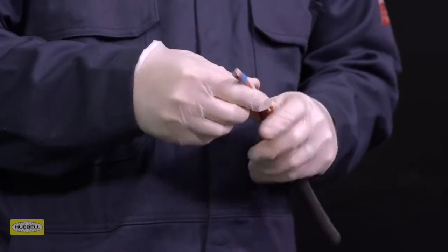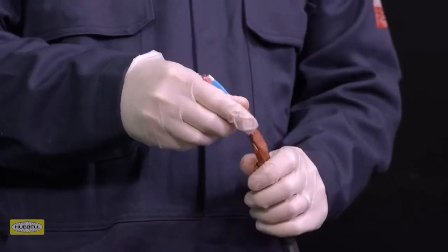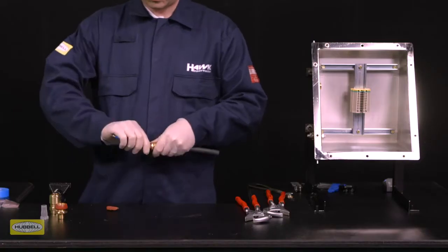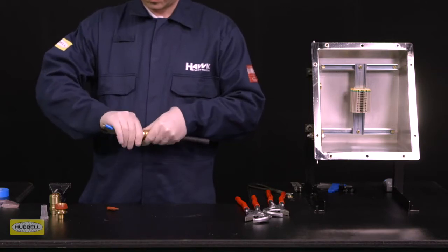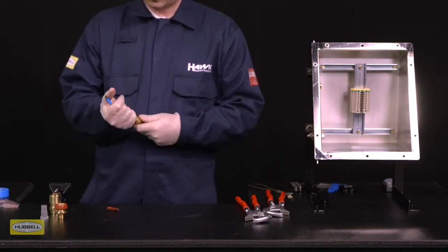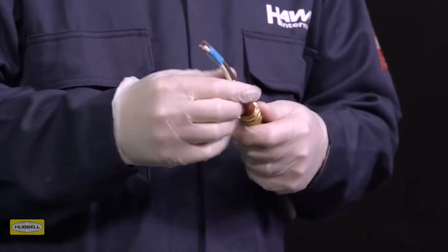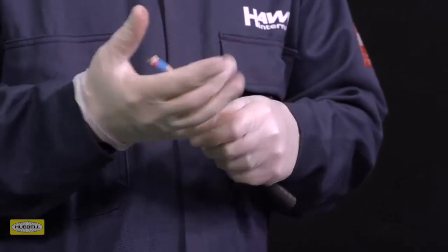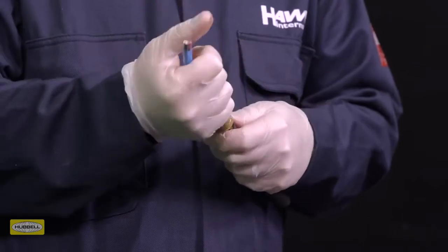Pack more compound around the outside of the conductors. Shape the compound using the palm of your hand. Tip: The compound should form a cone shape to aid installation and reduce the risk of voids during pot installation.